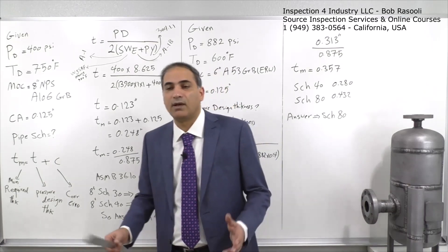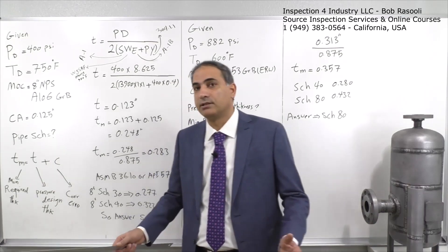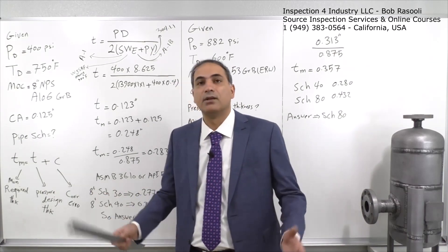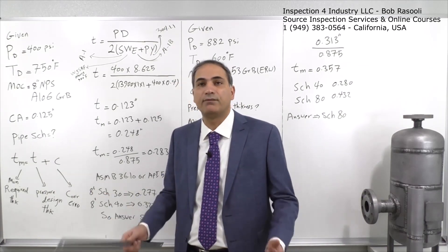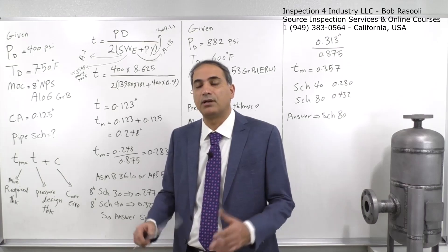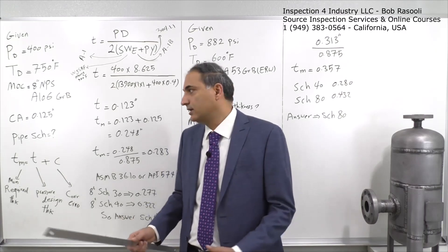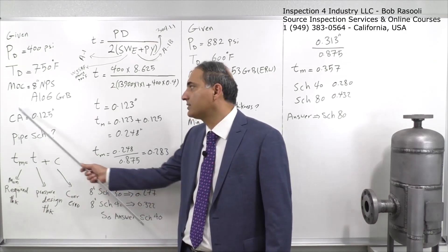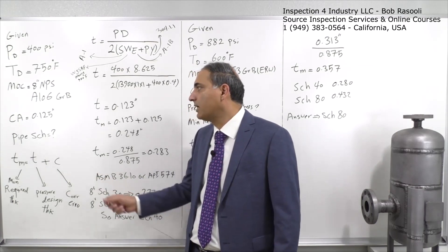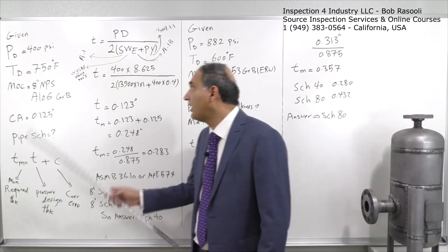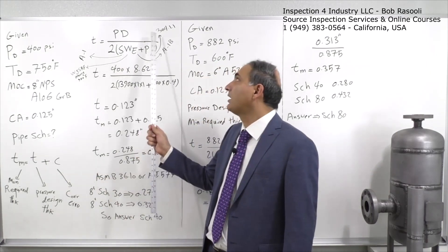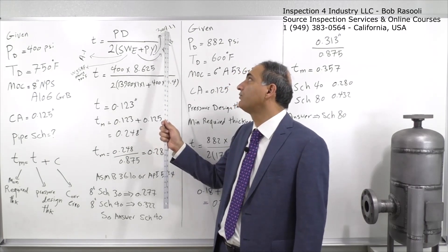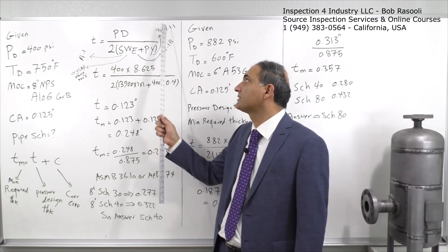Allowances may need to be added to the design thickness regarding the weight of the pipe, structural considerations, and other factors. However, the problem only specifies the corrosion allowance, so we will consider only that. To determine the pipe schedule, we refer to ASME B31.3 Section 304.1.1, which provides the formula.